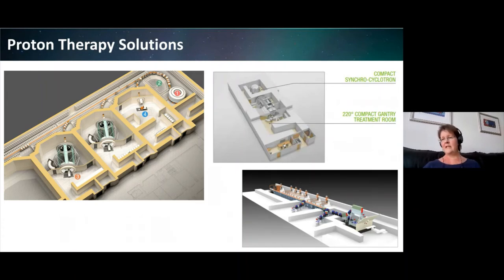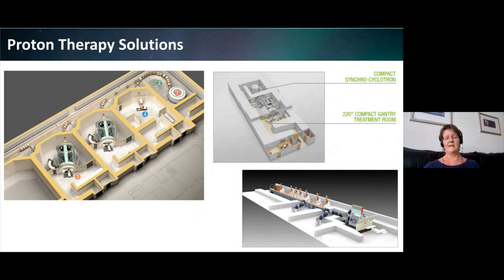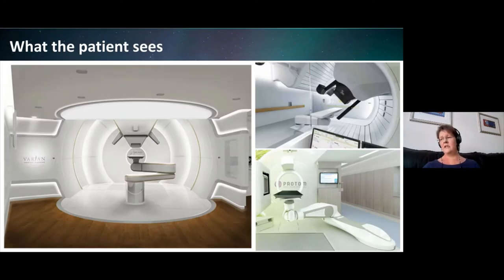There are also single-room solutions — for example, the IBA Proteus ONE — which include compact accelerators and less-than-360-degree rotation gantries with more patient movement. Novel solutions are also being developed, such as a linear accelerator arrangement based on the injector for larger high energy accelerators like the Large Hadron Collider, and it's also possible to accelerate protons using high-energy pulsed lasers. These solutions might be important where you're trying to fit proton beam therapy into a limited space. Ultimately, there's little difference in patient experience between proton beam and traditional x-ray beam therapy, with immobilisers and patient-specific moulds used in the same way.